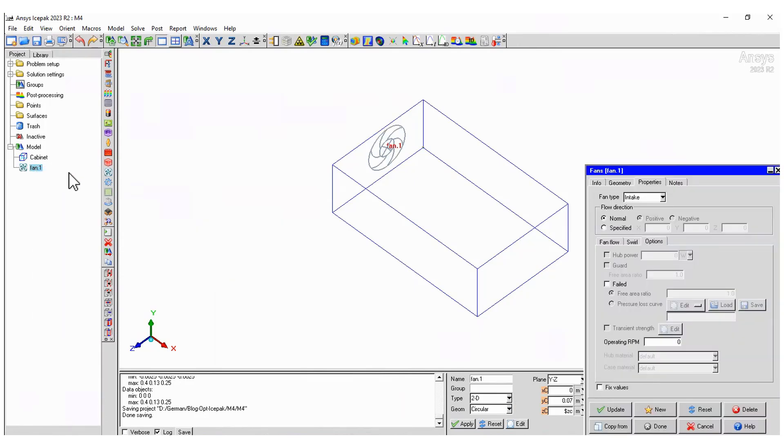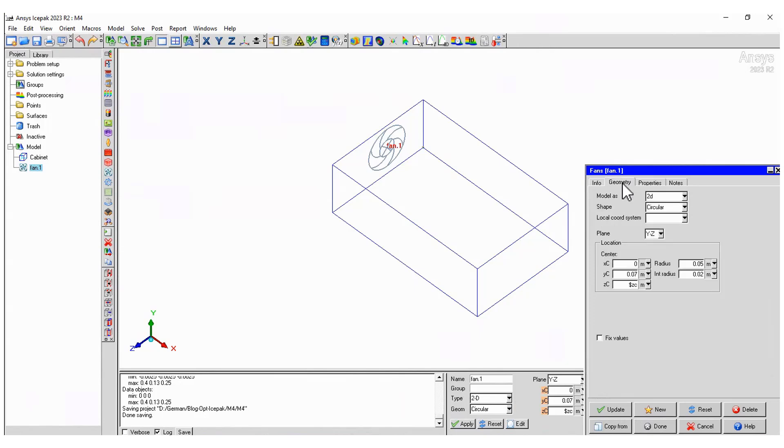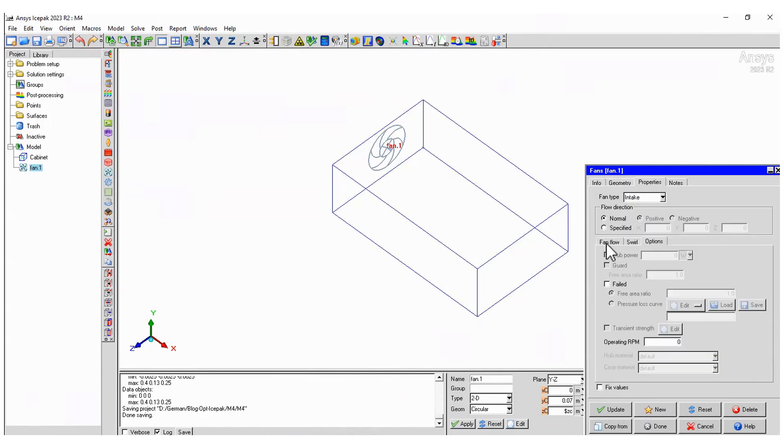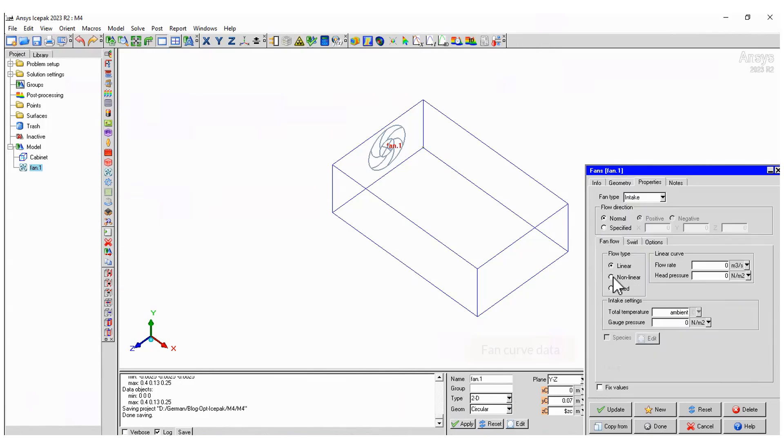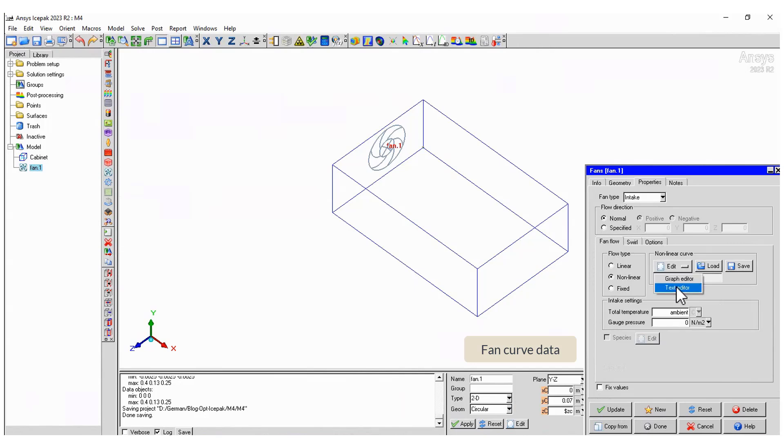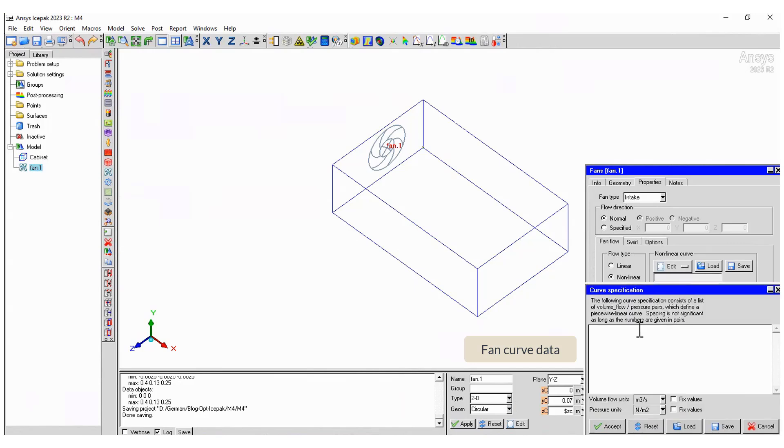In ANSYS Icepak we can work with fans having their characteristic curves. This is the case. In the properties tab select nonlinear and then text editor. Now type the coordinate pairs of the curve to define the pressure flow rate behavior.